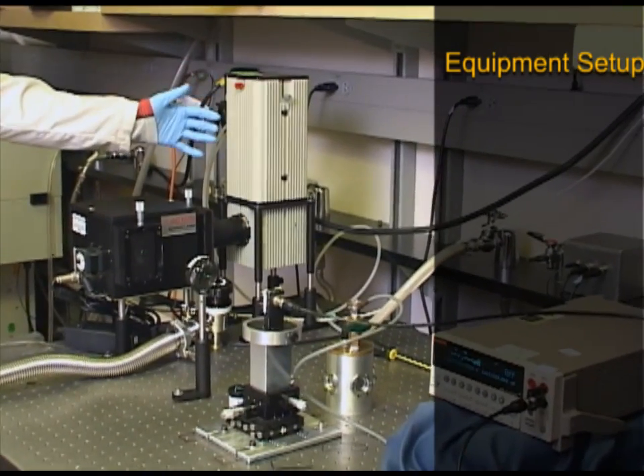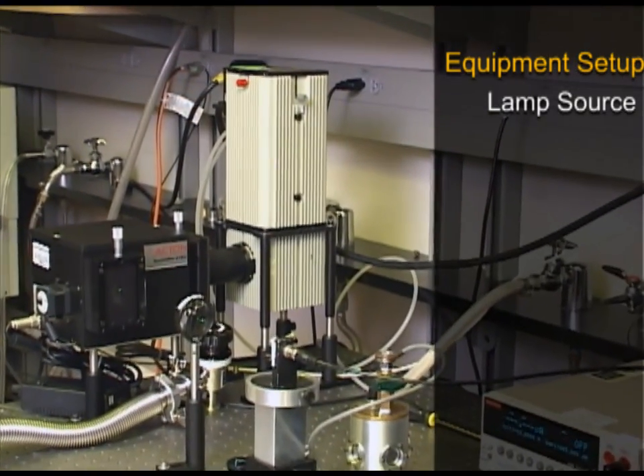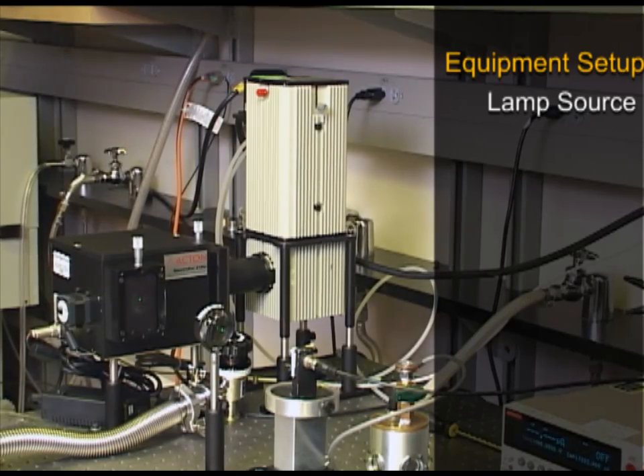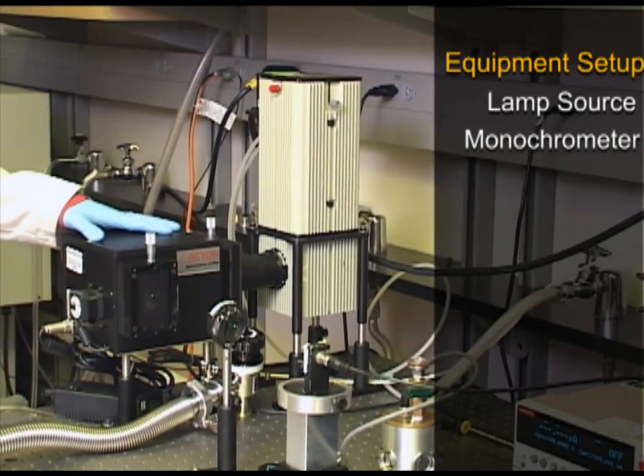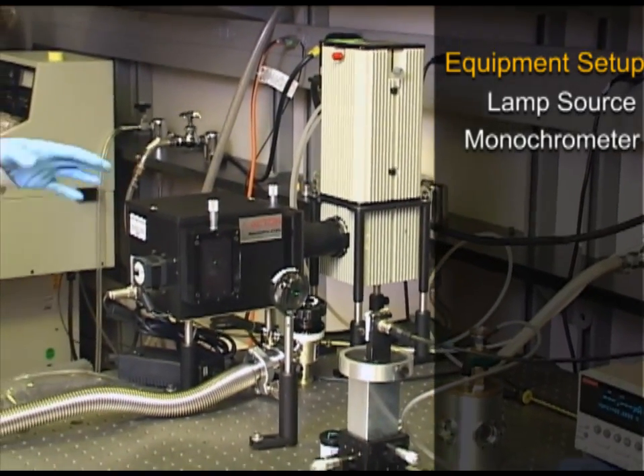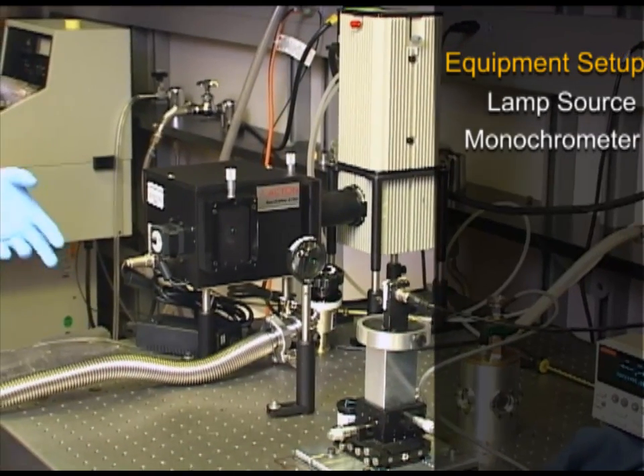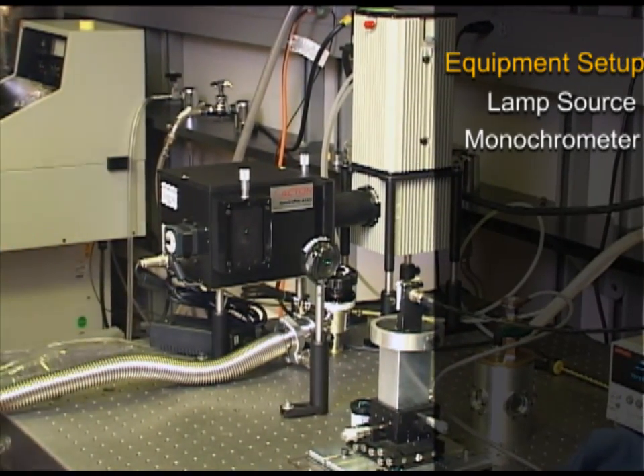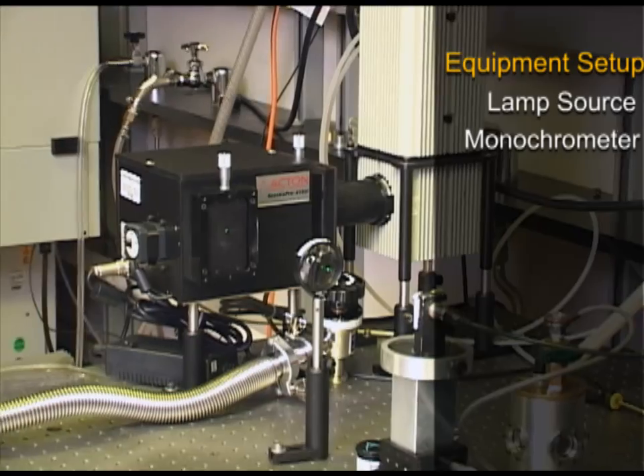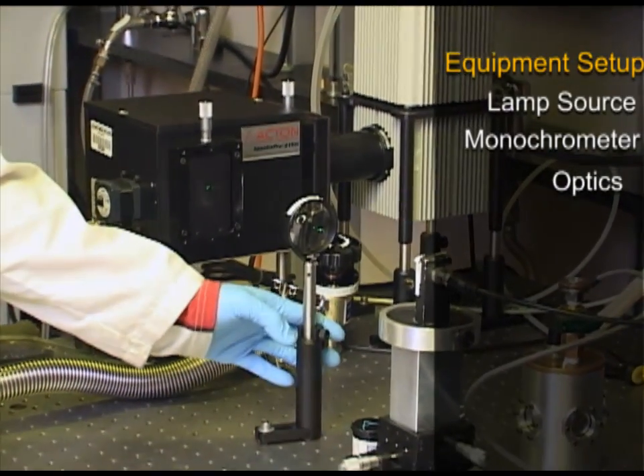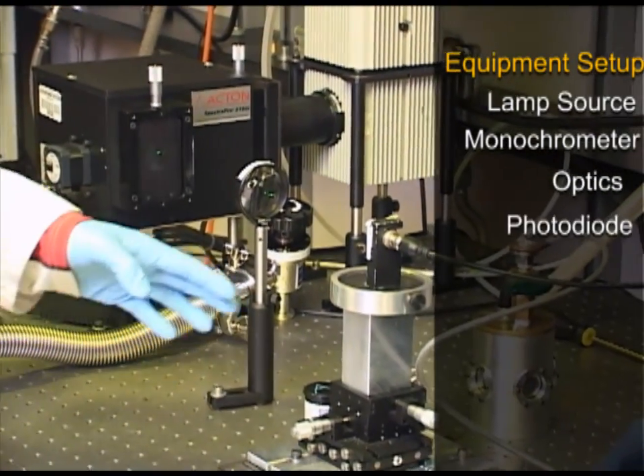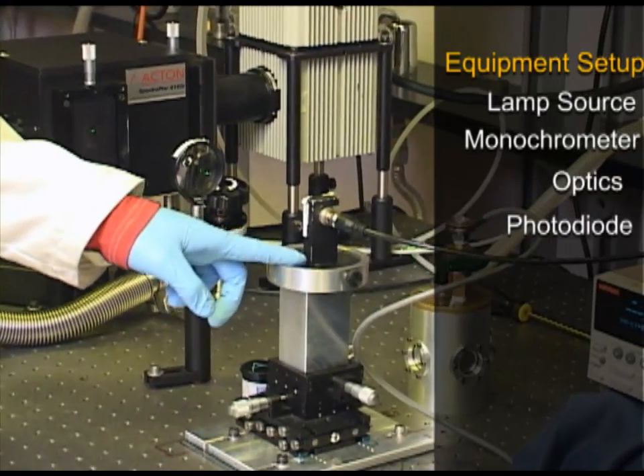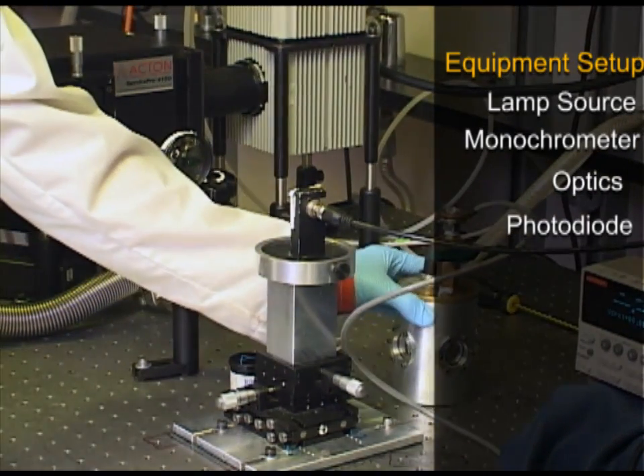First of all, we have the lamp source. Inside is a lamp and some optics to focus the light into the monochromator. And the monochromator allows us to select certain wavelengths of light to perform our spectral studies. We focus this light with some optics onto, in this case, a photodiode that's calibrated so we know how much light is coming out of the source.